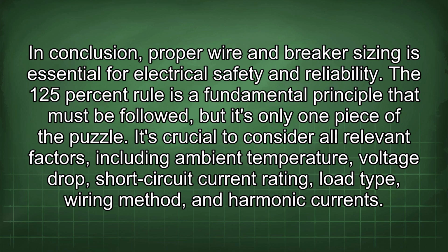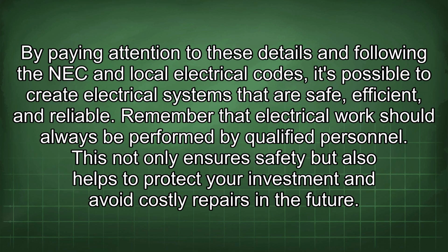The 125% rule is a fundamental principle that must be followed, but it's only one piece of the puzzle. It's crucial to consider all relevant factors, including ambient temperature, voltage drop, short circuit current rating, load type, wiring method, and harmonic currents. By paying attention to these details and following the NEC and local electrical codes, it's possible to create electrical systems that are safe, efficient, and reliable. Remember that electrical work should always be performed by qualified personnel.